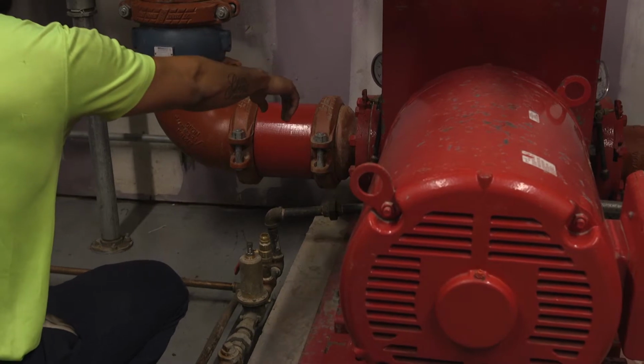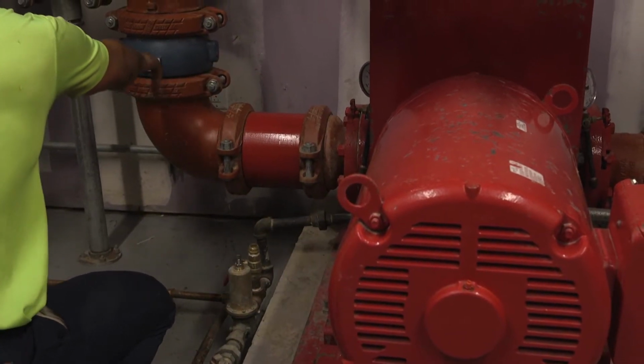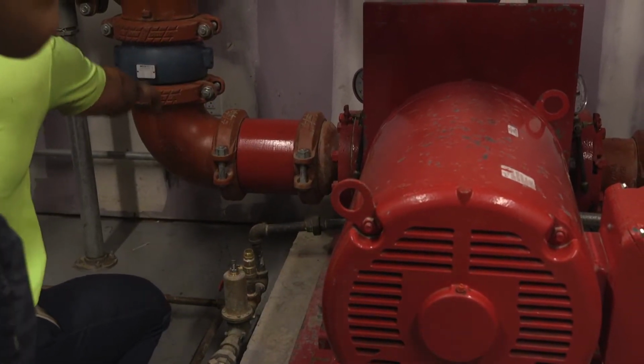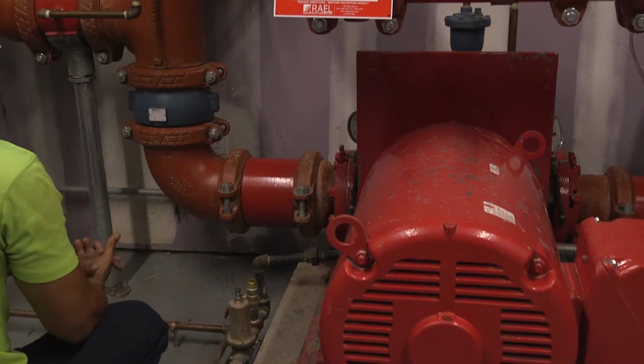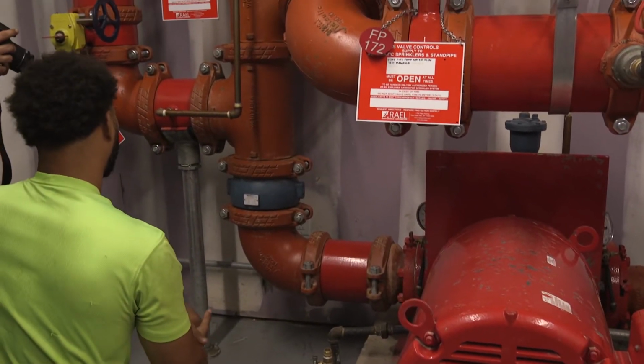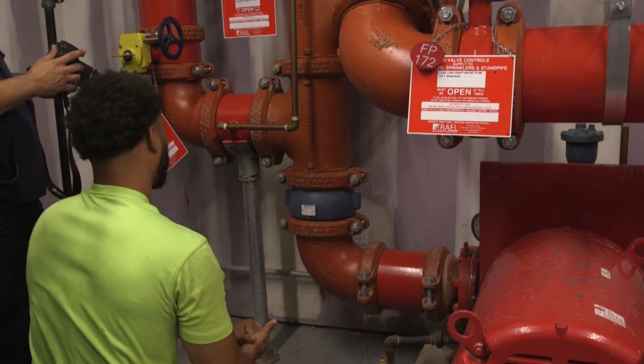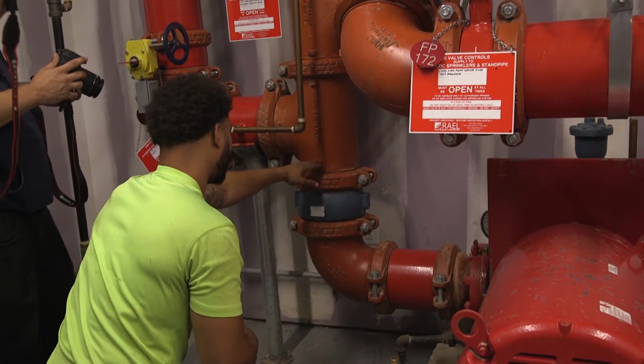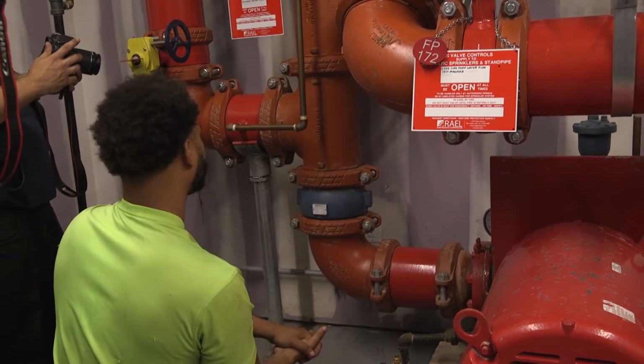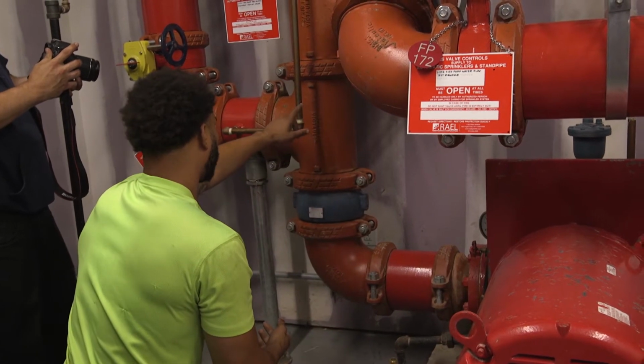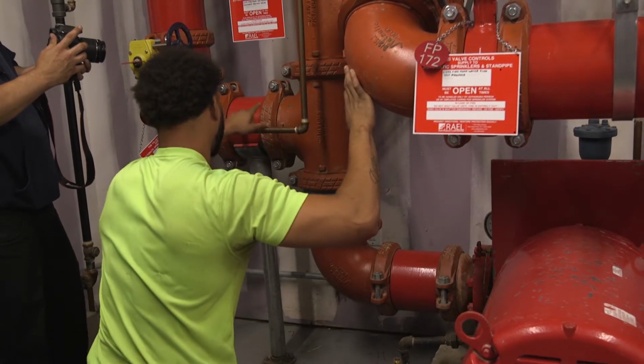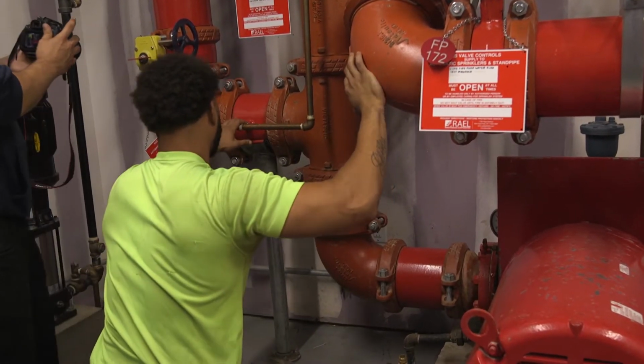So now we're looking at the discharge side of the fire pump. Here we have our discharge side check valve. Anything that goes above this check valve cannot flow in the opposite direction. And anything above this check valve is reading your live system pressure. If we keep flowing up, we're going to go to the left-hand side of the T. So here's our sensing line.